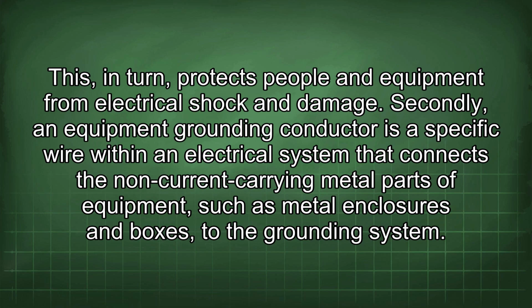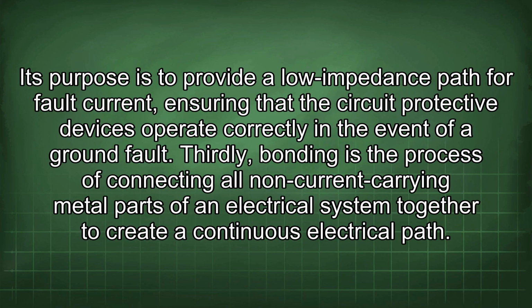Secondly, an equipment grounding conductor is a specific wire within an electrical system that connects the non-current carrying metal parts of equipment, such as metal enclosures and boxes, to the grounding system. Its purpose is to provide a low impedance path for fault current, ensuring that the circuit protective devices operate correctly in the event of a ground fault.